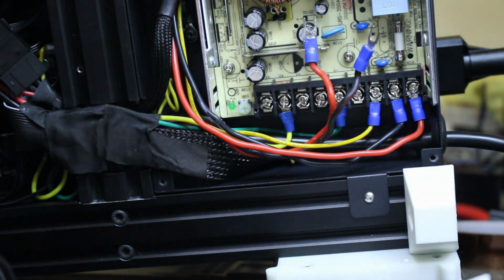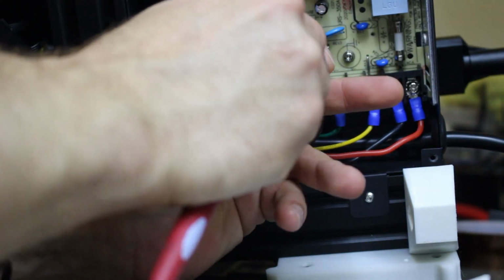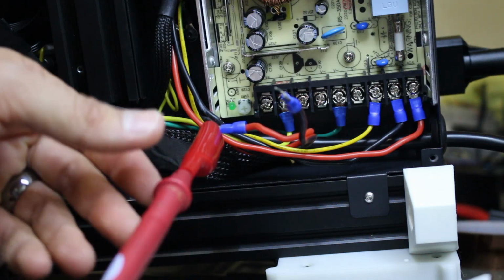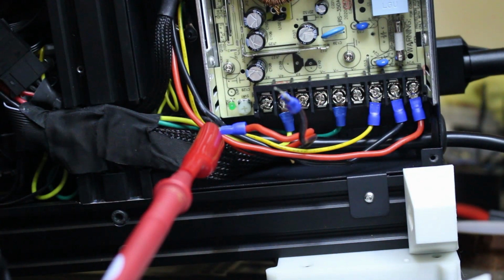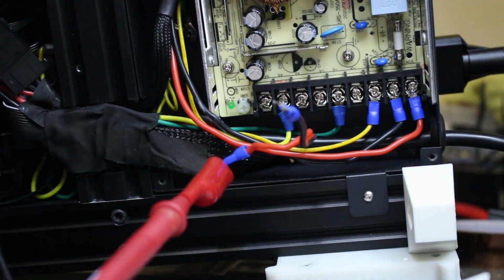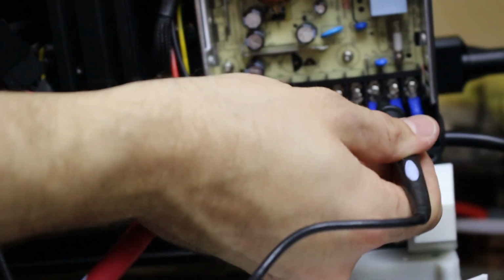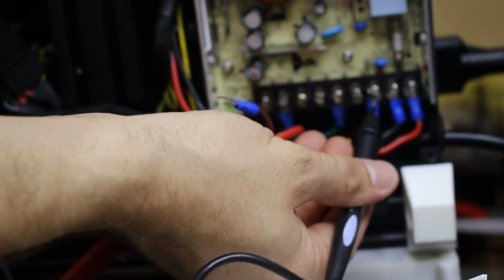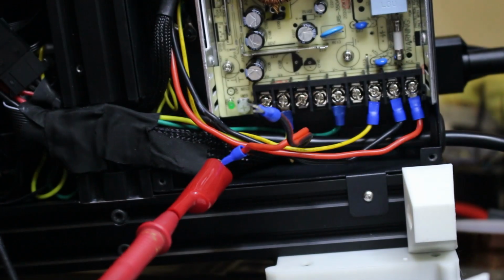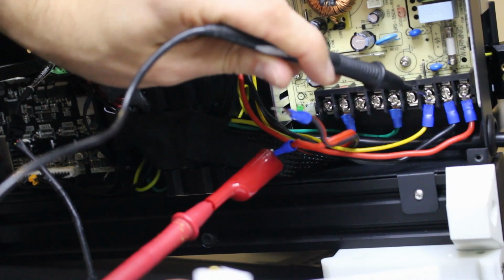If you were to unscrew these 2 wires here, careful not to touch anything else like I said, this isolates the motherboard and the 24 volt motherboard power from everything else. You should be able to connect your probe to 24 volts, and then take your other probe and touch earth with no connection, because they shouldn't be connected. There's no reason why those should be connected.